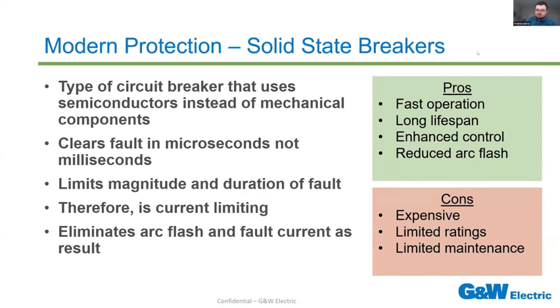So that goes in the pros. Fast operation. Once again, clears faults in microseconds. Long lifespan, as it doesn't rely on any mechanical parts, so it can last a longer period of time. Because it's electronic, you also will have enhanced control over the device and when it triggers and what it protects. And once again, it can virtually reduce or eliminate arc flash from your system.